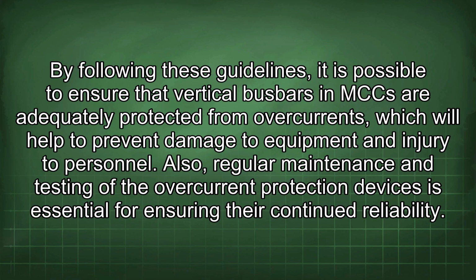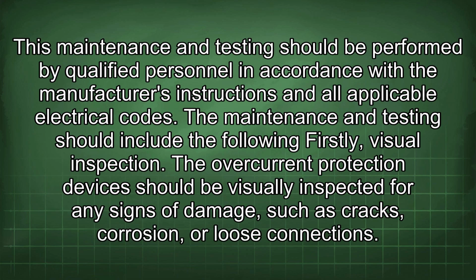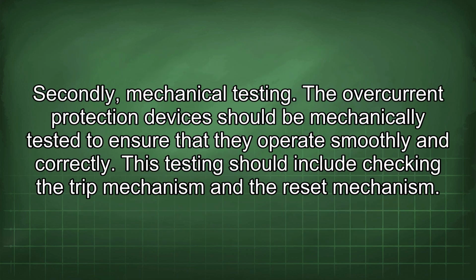Also, regular maintenance and testing of the overcurrent protection devices is essential for ensuring their continued reliability. This maintenance and testing should be performed by qualified personnel in accordance with the manufacturer's instructions and all applicable electrical codes. The maintenance and testing should include the following. Firstly, visual inspection. The overcurrent protection devices should be visually inspected for any signs of damage, such as cracks, corrosion, or loose connections. Secondly, mechanical testing. The overcurrent protection devices should be mechanically tested to ensure that they operate smoothly and correctly. This testing should include checking the trip mechanism and the reset mechanism.